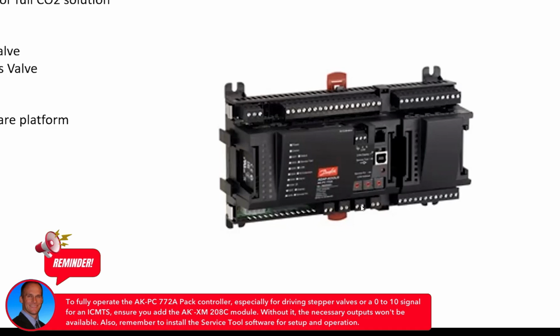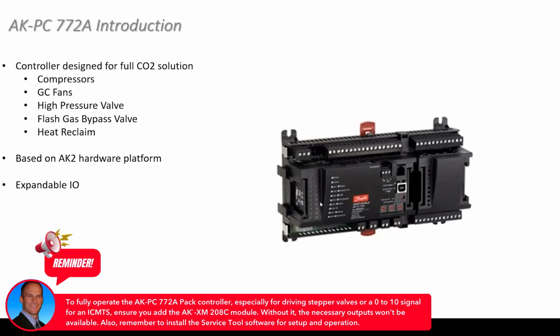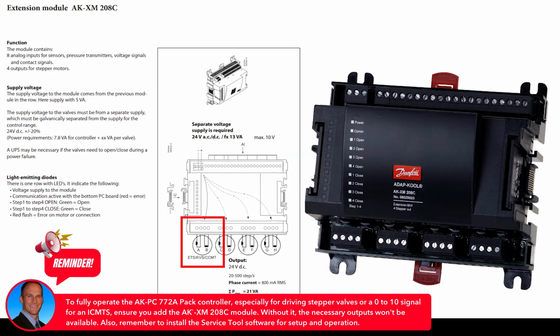But then we only have relays at the bottom of this. So when we're talking about driving stepper valves or a 0 to 10 signal for an ICMTS, the outputs for that aren't on the base module, I'll call it. We do have to add, and this is where the expandable IO comes into play. There's an optional module that you would just snap right onto the end. There's tracks at the right side, you can't see it in this depiction, but there's tracks on the right side of the pack controller, and that optional module for the stepper valve outputs could just snap right onto the end of the main baseboard here to offer those points.